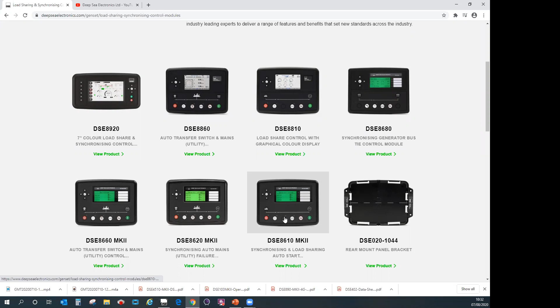This starts and it synchronizes with whatever's on the load, closes its breaker, and then it will load share with other 8610s. If we look at an 8620, very similar principle, but this just synchronizes and load shares with one main supply. So imagine you've got a building, and the load on the building itself has got such a high load that the mains can't support it.